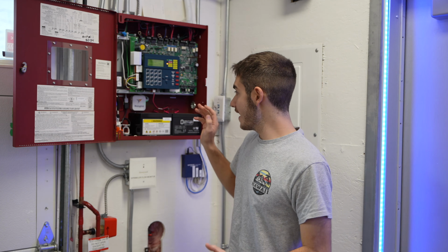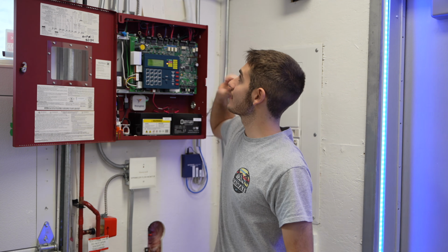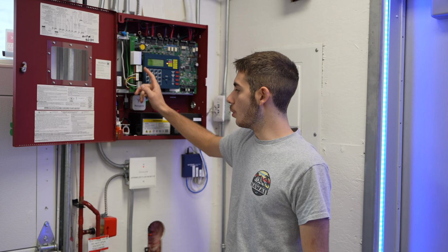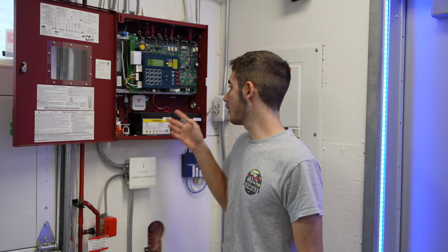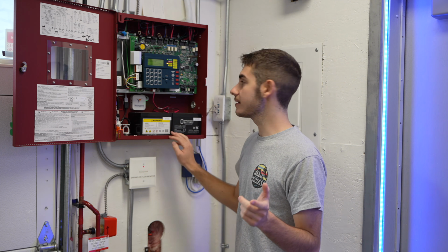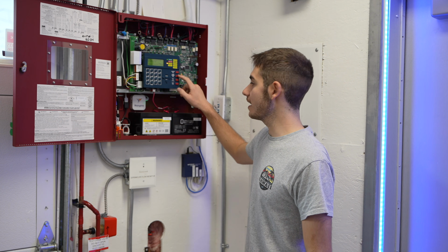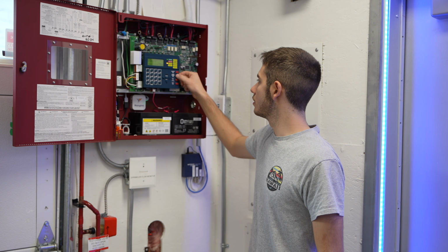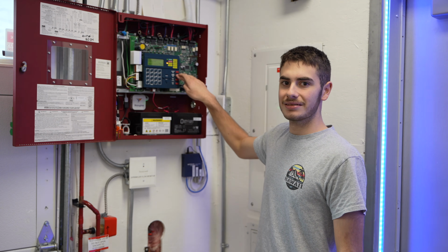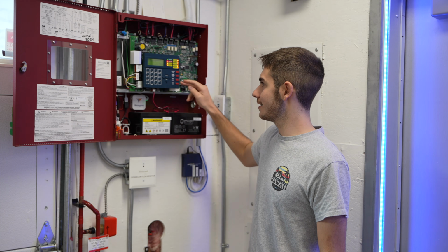However, what people are saying, as I mentioned, is if I was to make this set as non-silenceable, it would work where it wouldn't go off on drill. The side effect is I can't silence it. So let's see if that's true. If I hit alarm silence, if I had changed it, it wouldn't silence. Which it's not. So that means the only way to stop it is to reset.